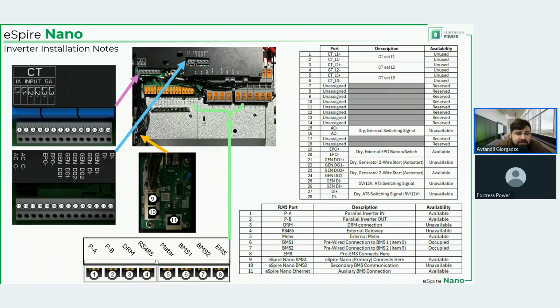EPO plus and EPO minus, number 19 and 20, that will be where you connect your external emergency power off button or switch. Gen DO1 plus and Gen DO1 minus. DO stands for digital output. So generator 2-wire start is Gen DO1 plus and Gen DO1 minus, and same for Gen DO2 plus and Gen DO2 minus. But DO1 plus and DO1 minus are not used, but DO2 plus and DO2 minus are used for generator 2-wire start. Then you have Gen DI plus and DI minus.